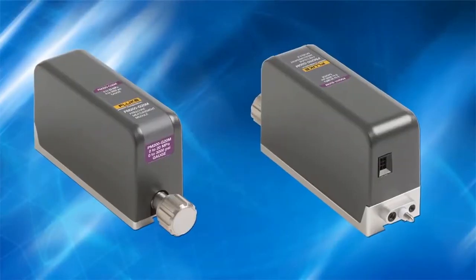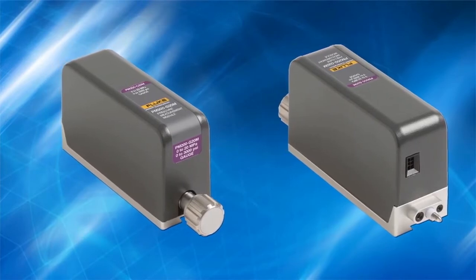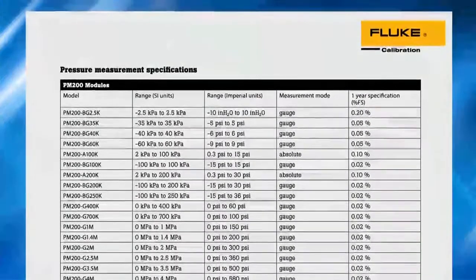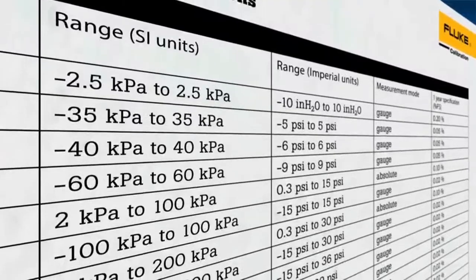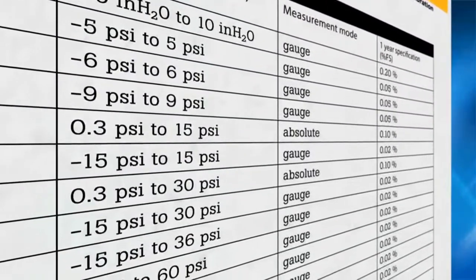The 2271A uses Fluke Calibration PM200 modules to measure pressure. With over 20 ranges to choose from, you can use the 2271A from vacuum to 20 MPa, or 3000 PSI.